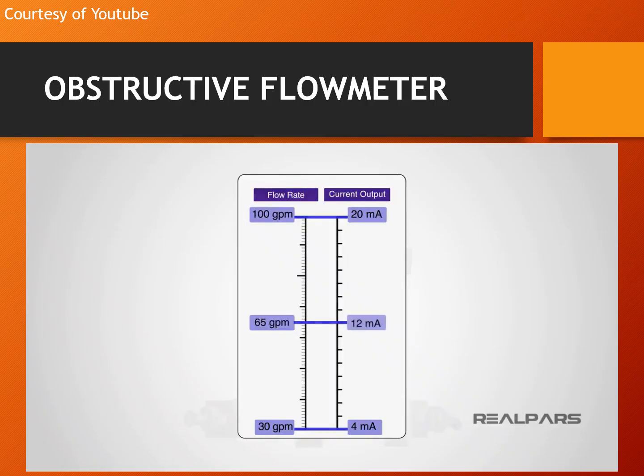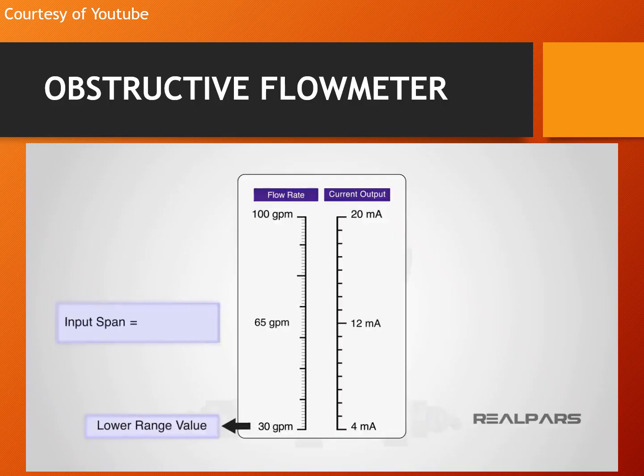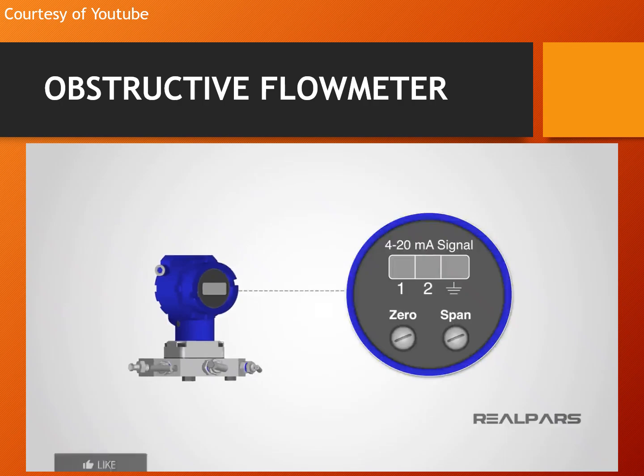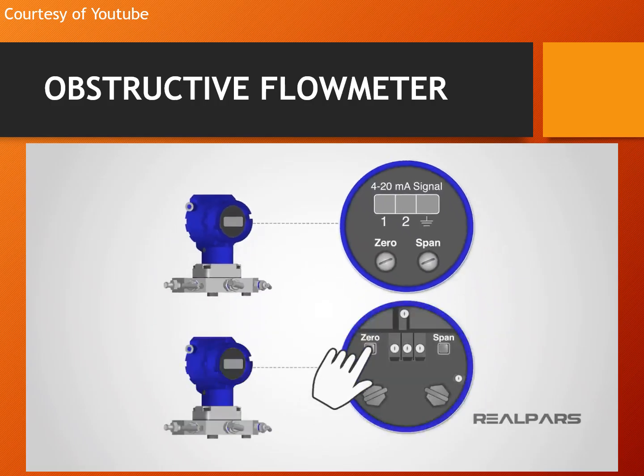The input span of an instrument is simply its lower range value, often referred to as LRV, subtracted from its upper range value, often referred to as URV. For example, the span of the input range of 30 gallons per minute to 100 gallons per minute is 70 gallons per minute. Zero and span are the names of the adjustments made in order to calibrate an instrument. There are many ways to adjust zero and span. For example, they could be physical adjustments, such as potentiometers, or software-based push-button adjustments.